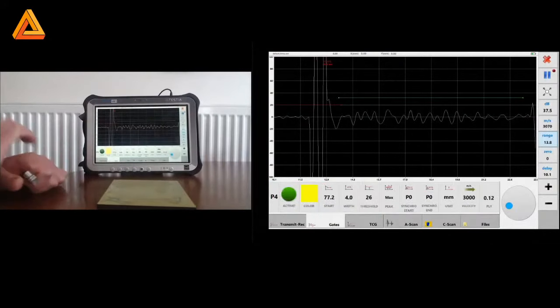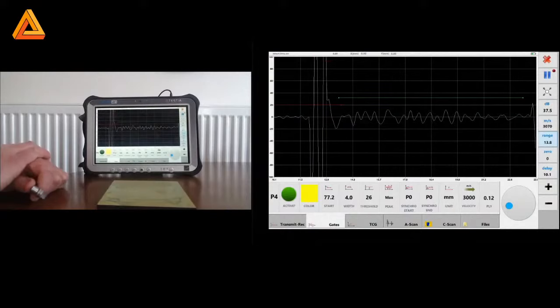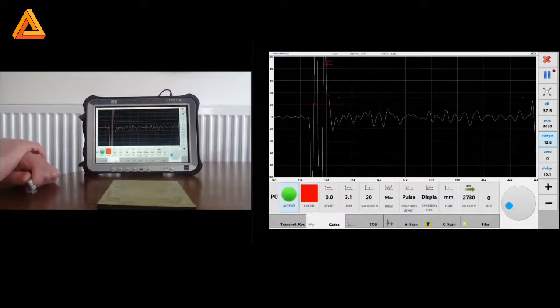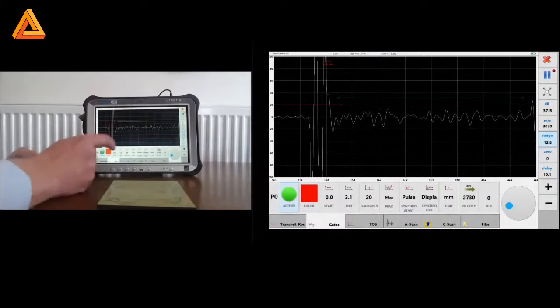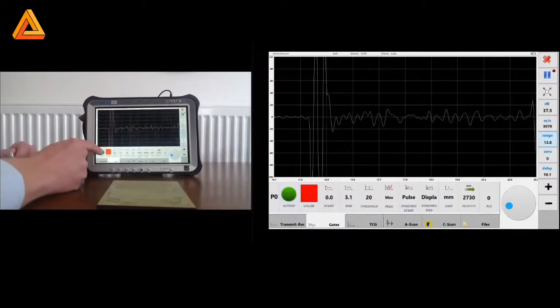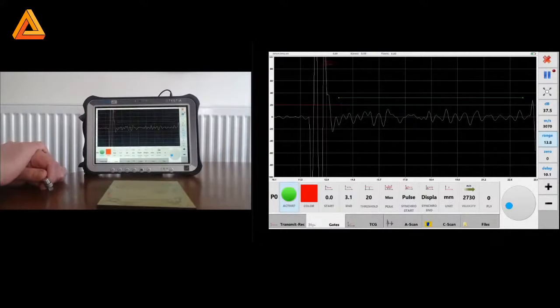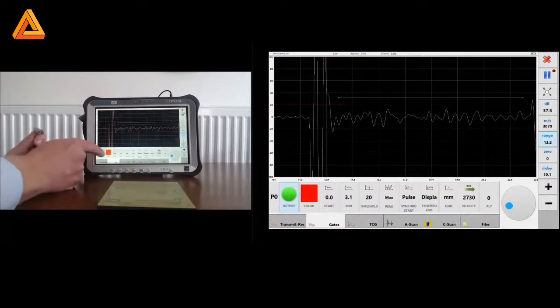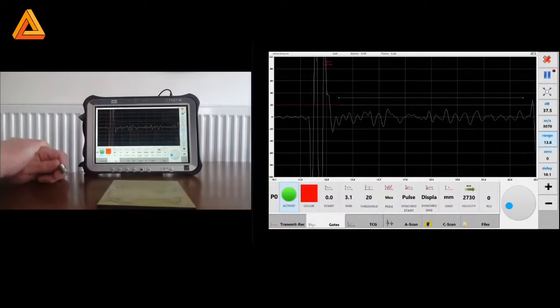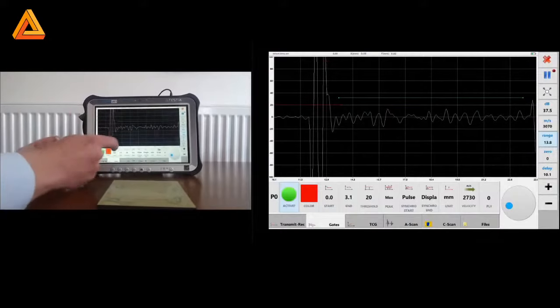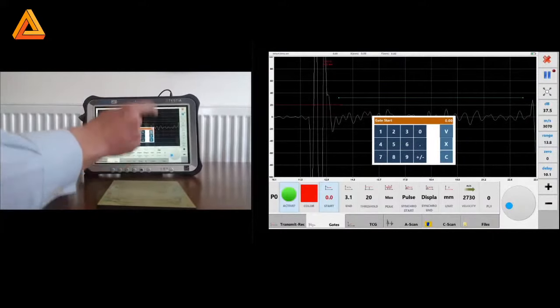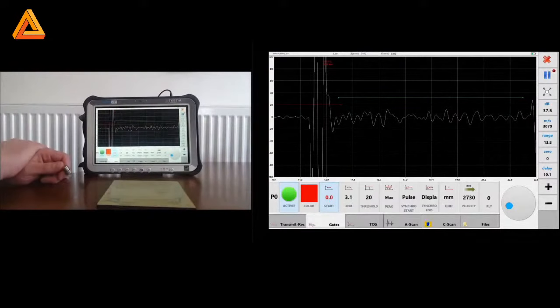Coming across to our gate menu, the UE1 has five gates available: P0, P1, P2, P3 and P4. Each one can be activated or deactivated by simply pressing the large green button. When it's illuminated, that gate is now active. The gate position can be manipulated by altering the start, end and threshold, and again we can either do these as a direct read or using the jog wheel or the plus and minus for more fine adjustments.